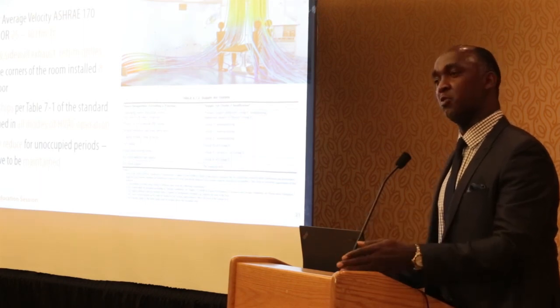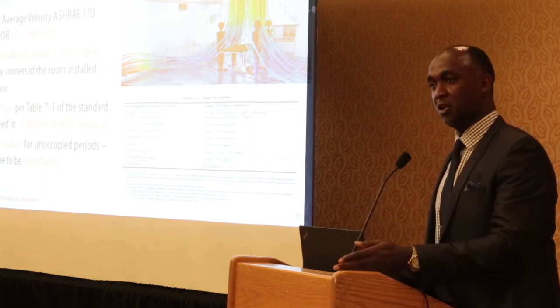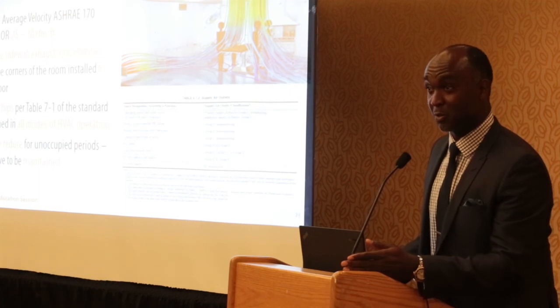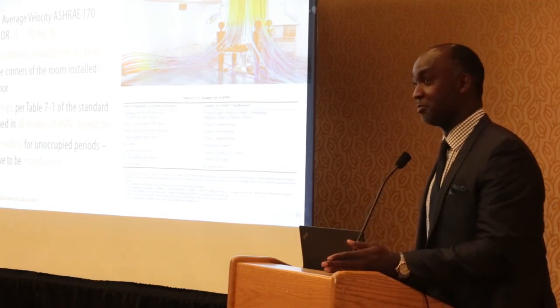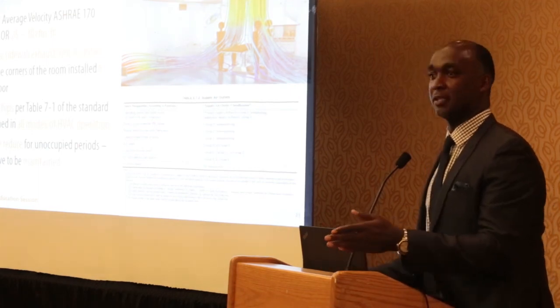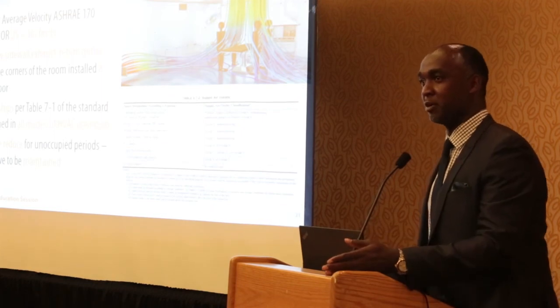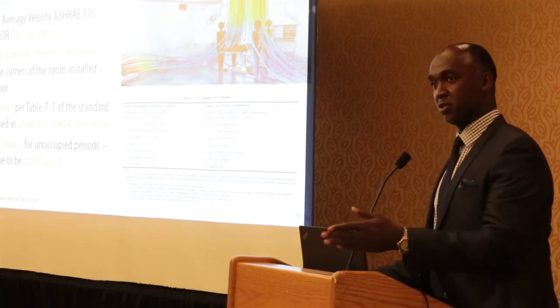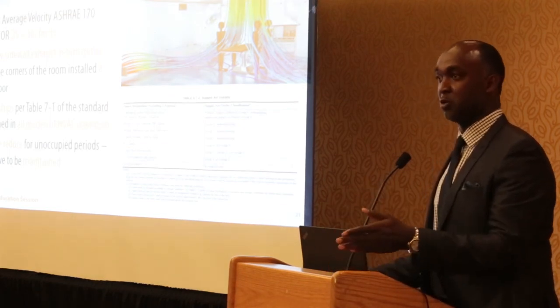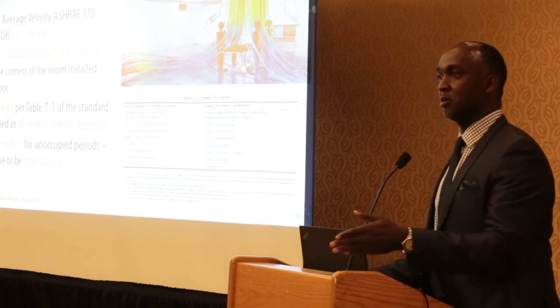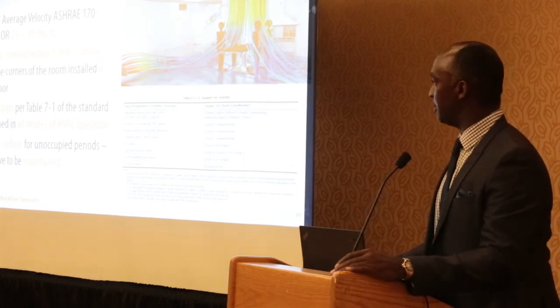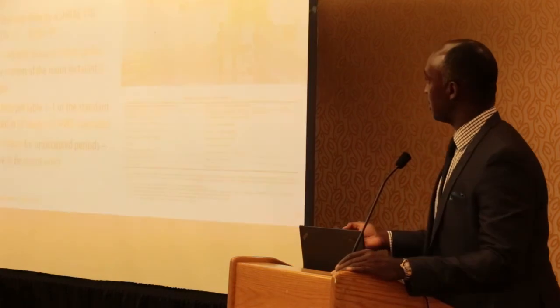But you still have to maintain the conditions. It still has to be positive so that you don't introduce any unwanted bacteria or microorganisms from the outside into your OR room. You have to make sure that the humidity level is still maintained, but you can reduce the air change in the space.